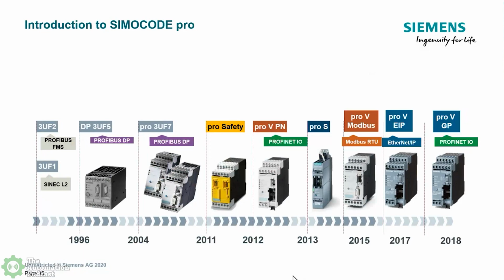But notice that we started it initially in 1996. And if you look at it really close, that unit there has the CT and the brains all integrated into one piece. So if eventually the brains, because there are contactors in this, wore out, then you are unwiring the motor leads, and then you're, of course, undoing all the control wiring too to replace it. In 2004, we switched up the form factor to where now the CT and PT is a separate unit. It is not integrated to it.